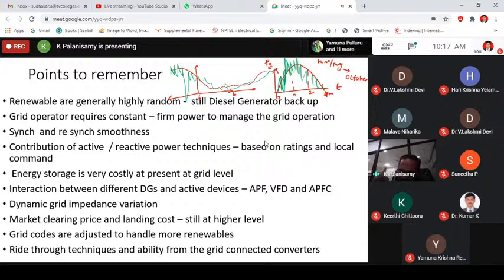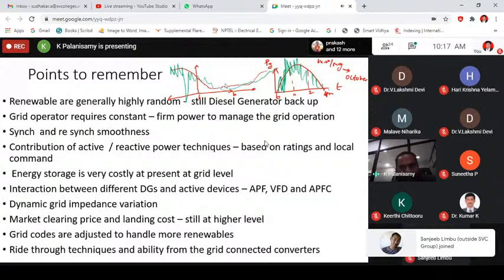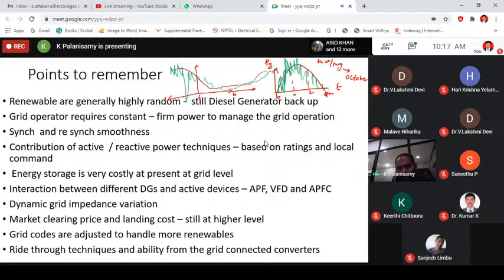though we have solar and wind, maybe as a captive power plant or as a big industry, you can have your own big solar plant or big windmill. But still, you may need a diesel generator backup. If you are relying only on solar and wind, for example, if you have a 1 megawatt load, I'm just giving an example, and you have more than 1 megawatt of solar or wind, or combined maybe around 1.5 megawatt, you may still not be able to supply this 1 megawatt constantly to the load. That's why we need a diesel generator backup. When good sunshine and good wind come, you may get more than 1 megawatt also.